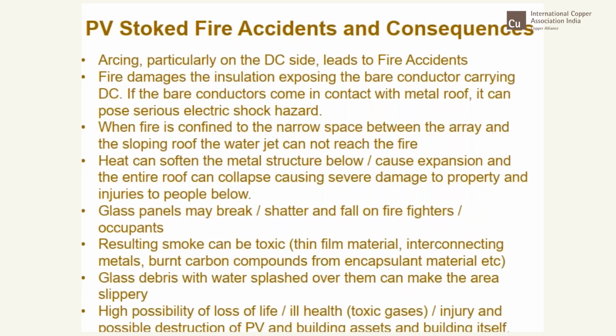So how can PV fire accidents take place, and what are the consequences? Arcing, particularly on the DC side, leads to fire accidents. Fire damages the insulation, so even though the neighboring cable may be all right, it could get stripped, exposing the bare conductor carrying DC. Now, if this bare conductor comes into contact with a metal roof, and many times metal sheets are used in factories, it can pose a serious electric hazard because the entire metal roof will become alive.